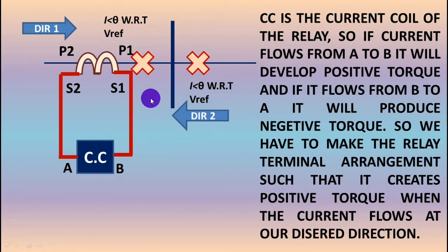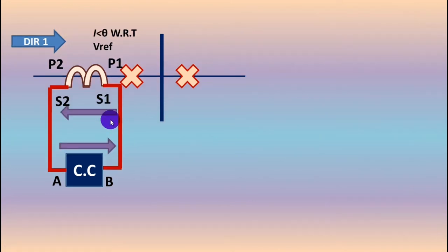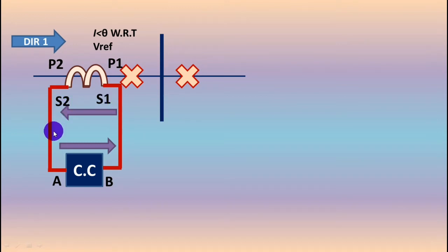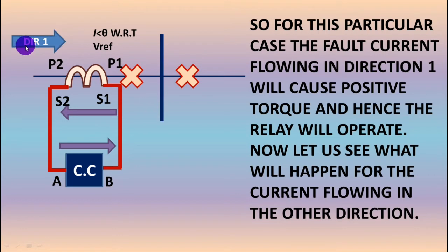This relay will create positive torque when the current flows from A to B through the current coil, and will create negative torque if the current flows from B to A. We have to ensure that for our desired direction the current creates positive torque in this current coil. Our desired operating direction is direction 2 — the relay should operate for direction 2, not direction 1. Let's see whether this connection satisfies that. For direction 1, the current is flowing from P2 to P1, so in the secondary there will be current from S1 to S2, flowing from A to B — generating positive torque.